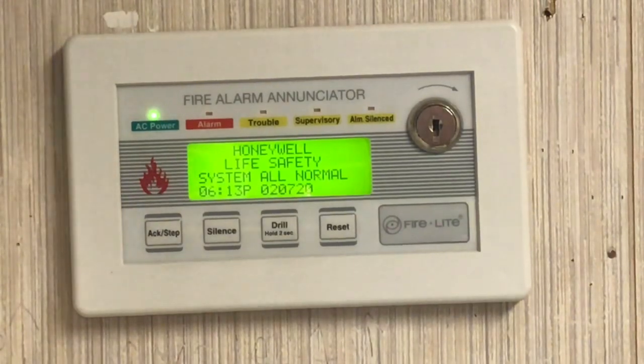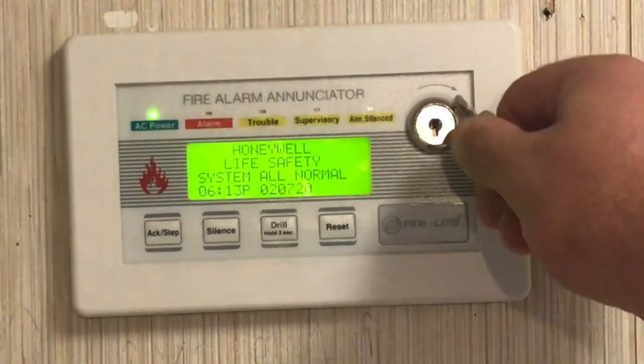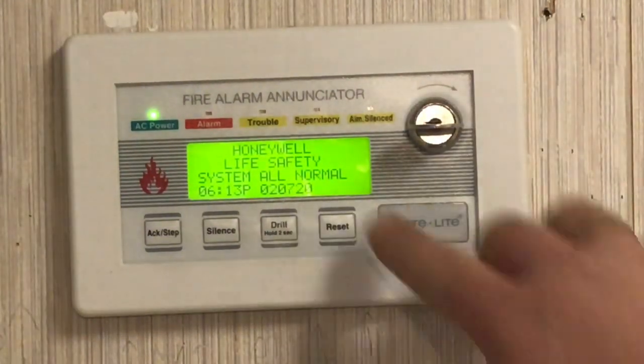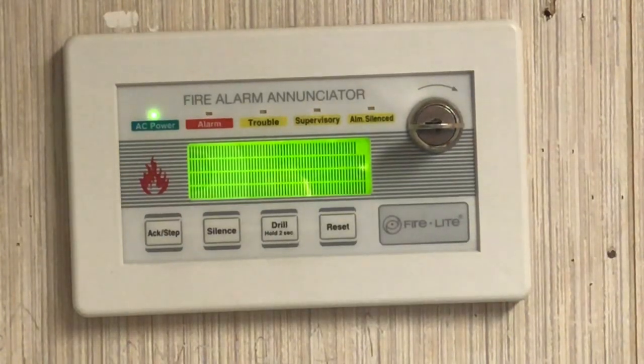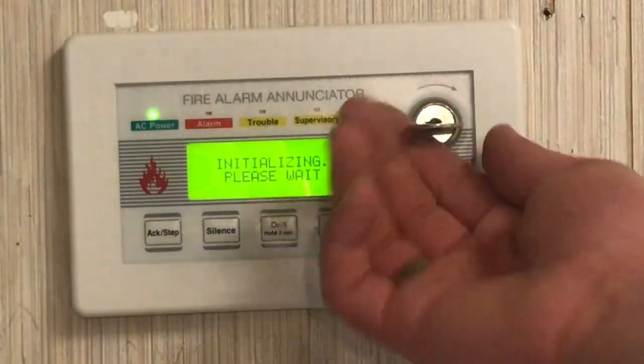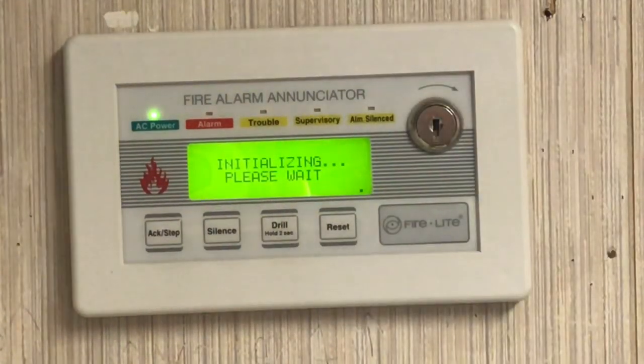Now it's time to test the annunciator. The AC power LED is illuminated and the LCD says the exact same thing as the main fire alarm control panel. We're going to put our key in the annunciator, turn it, and press Reset. We now know the annunciator works and is operating properly — reset in system — and now the system is initializing. Once you're done, take your key out. If you have any questions, please feel free to ask. Hope this video helped — talk to you soon.